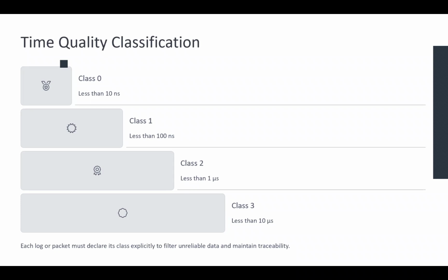Now class 1 is when we have precision up to 100 nanoseconds error. This class is appropriate for systems using GNSS or disciplined crystal oscillators. Okay, and it's typically used for 5G base stations or SCADA systems. Data in this class is still considered high integrity and is reliable for control and protection.